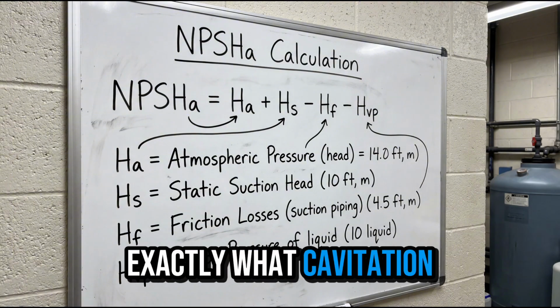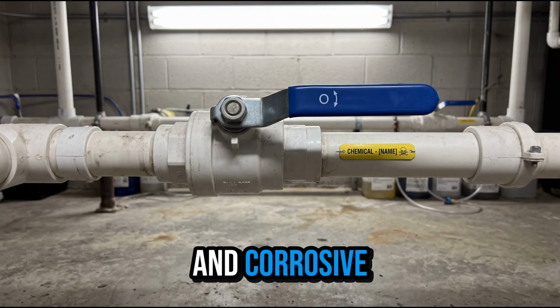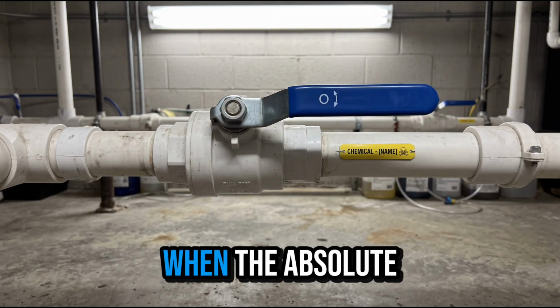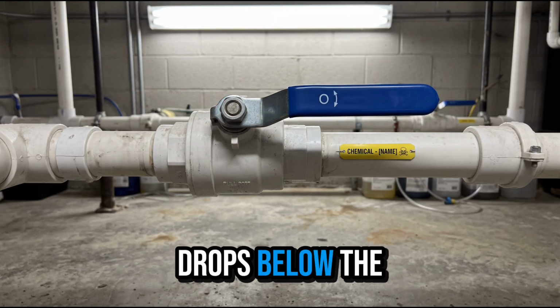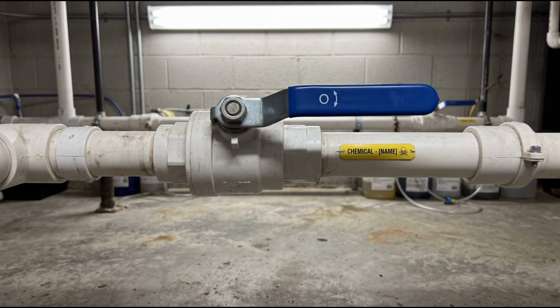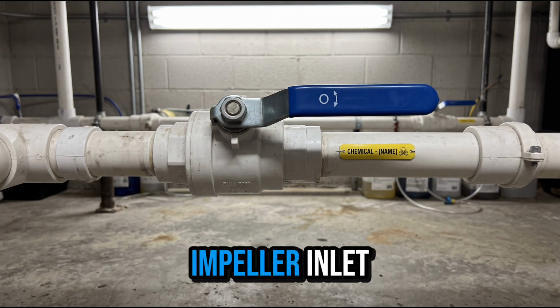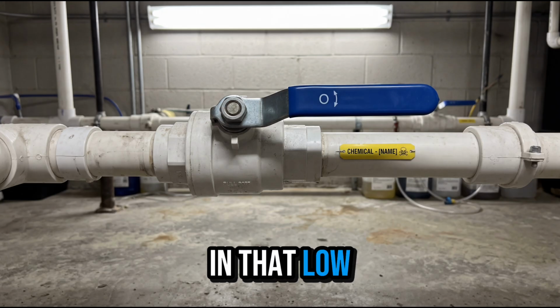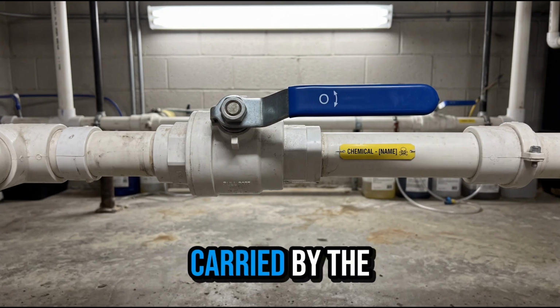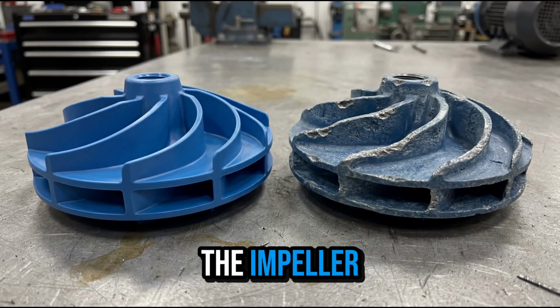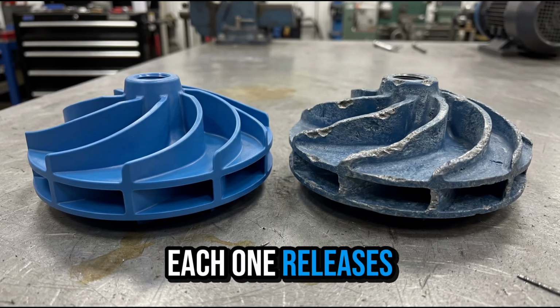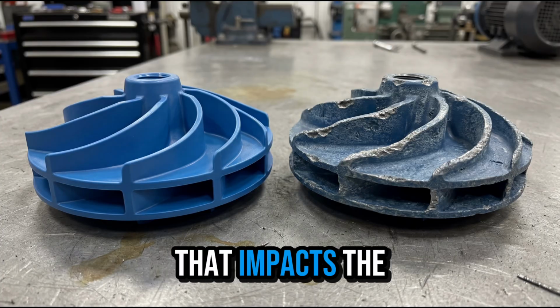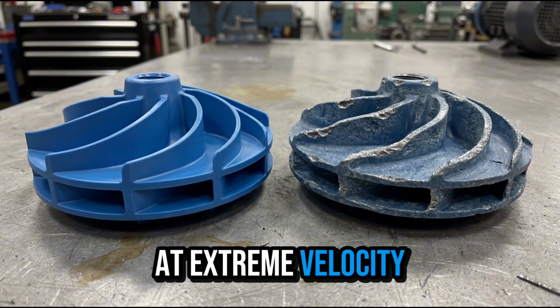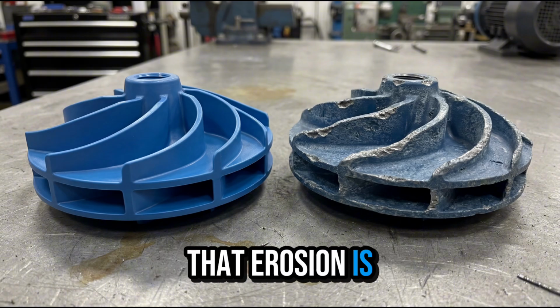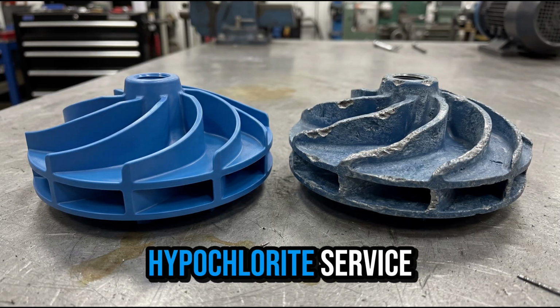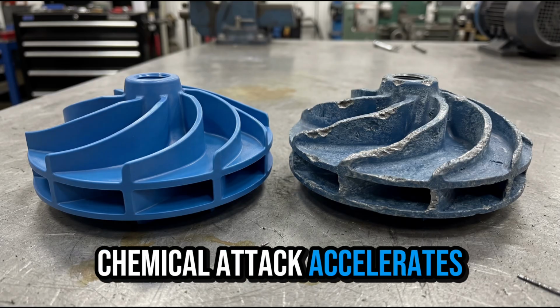Let me explain exactly what cavitation is and why it is so destructive in corrosive chemical service. When the absolute pressure at the pump inlet drops below the vapor pressure of the liquid being transferred, the liquid partially vaporizes at the impeller inlet. Vapor bubbles form in that low pressure zone. Those bubbles get carried by the fluid into the higher pressure region of the impeller. When they collapse, each one releases a high-energy microjet that impacts the impeller surface at extreme velocity. In clean water service, that erosion is slow. In sodium hypochlorite service, chemical attack accelerates.